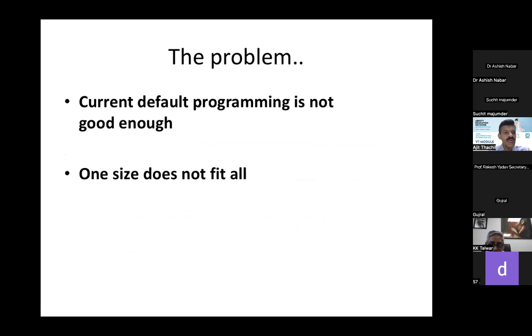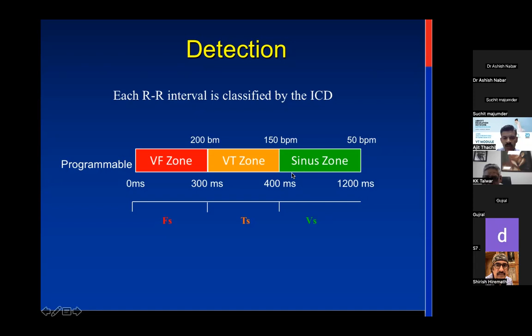First, detection. Every RR interval is classified by the ICD as being in the ventricular fibrillation zone, the ventricular tachycardia zone, or the sinus zone. For example, in this particular example, anything from 150 to 200 beats per minute, that is 300 to 400 milliseconds, is called VT. Anything more than 200 beats per minute, that is cycle length less than 300 milliseconds, is called VF. It may not actually be VF; whatever is in the VF zone is just called VF. Anything slower than this rate is called sinus, or VS.